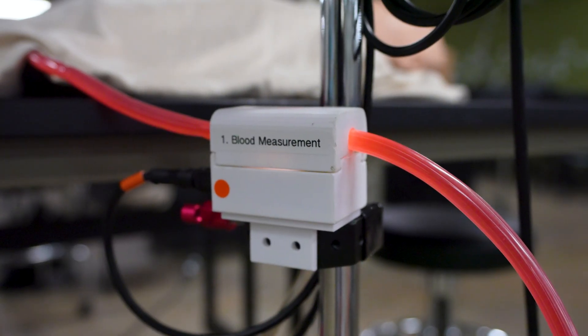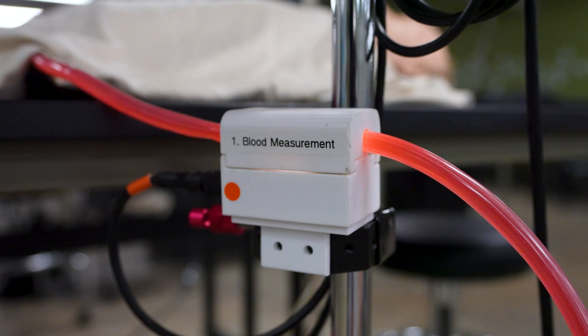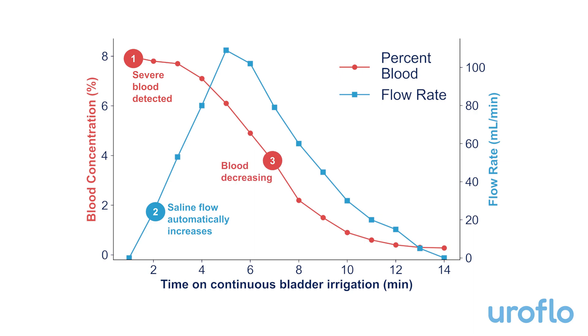Let's take a quick look at a demonstration to see Uroflo in action. Uroflo's hematuria color sensor quantitatively measures the blood concentration in the patient's output urine with over 95% accuracy. This graph shows Uroflo's feedback control system. Upon detecting excessive bleeding, the device increases the saline flow rate into the bladder to wash away the blood. As the bladder is irrigated, the blood concentration tapers off over time, and our device responds by slowing down the flow rate.